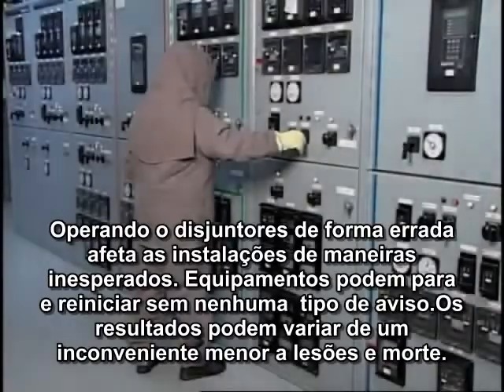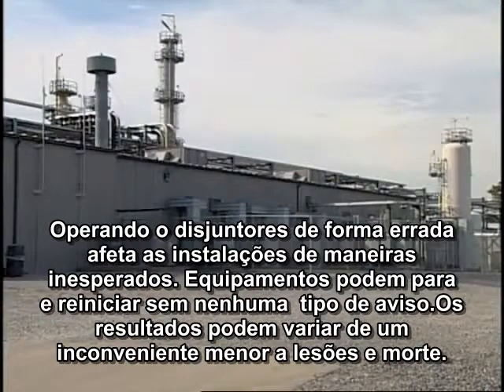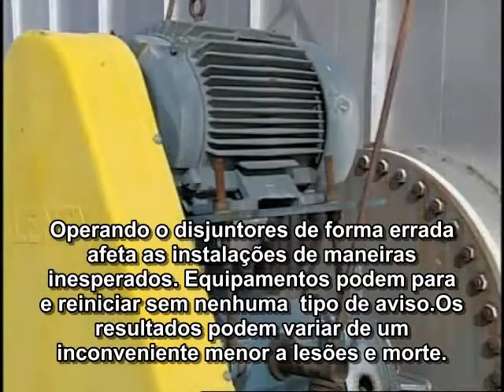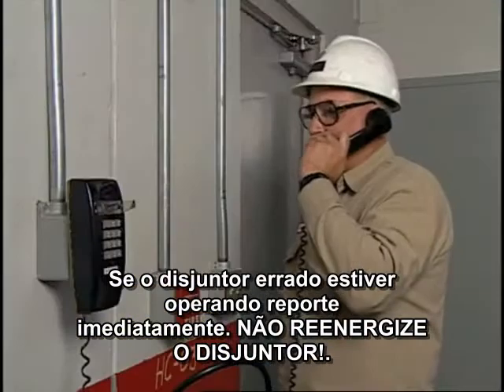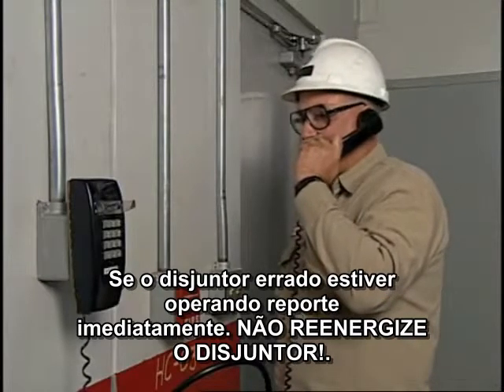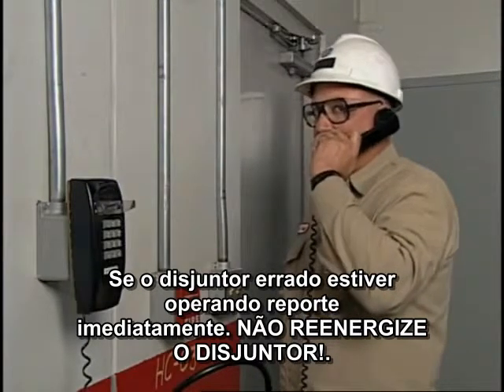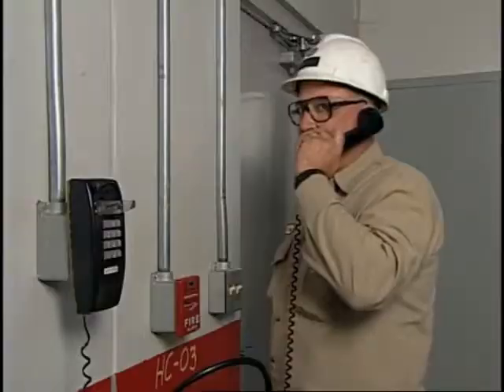Possibility of operating the wrong breaker. Operating the wrong breaker affects normal plant operations in unexpected ways. Equipment may stop, then restart without warning. Results can range from minor inconveniences to injury or fatalities. If the wrong circuit breaker is operated, report it immediately. Do not re-energize the breaker.